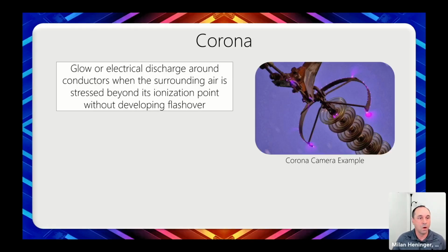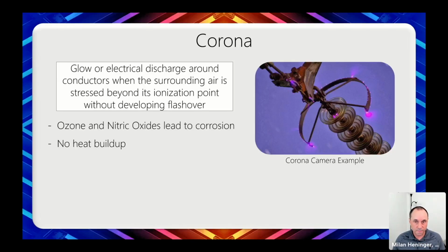So corona is that glow or electrical discharge around conductors when the surrounding air is stressed beyond its ionization point. So it's not flashing over, it's just the molecules in the air are kind of getting torn apart. And that creates ozone, and it can also create nitric oxides. This can lead to corrosion. So we need to make sure that the corona that we're experiencing is something that we can consider normal, because it can be hard to detect with thermography, and it can be voltage dependent.